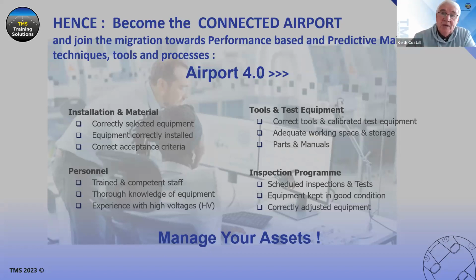So what we have out there, to be able to illuminate the lights correctly in accordance with the standards, we have to put a big pressure, a voltage, onto that circuit to drive the standard system of 6.6 amps. Now there are other systems in the marketplace—not everybody uses a constant current system. There are parallel systems, lower current systems, etc. So other systems are available, but most of the world is standardized on a 6.6 amp series circuit system.